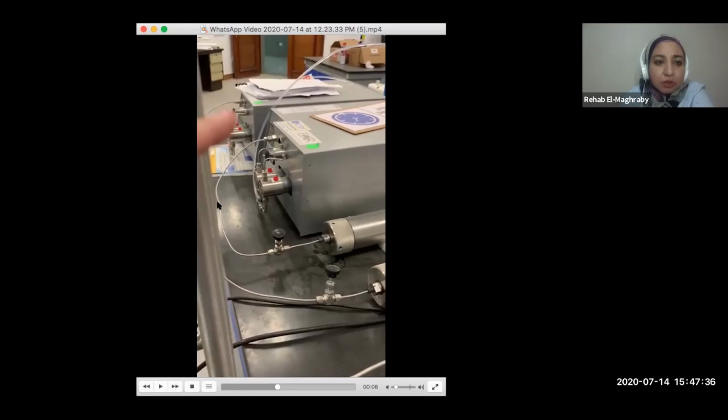I'm sorry, water is injected through this accumulator. For this, you have to take care of your piston. You don't want to ruin it. So it is important to use the accumulator. It's better to use the accumulator, and you just use deionized water for your injection.